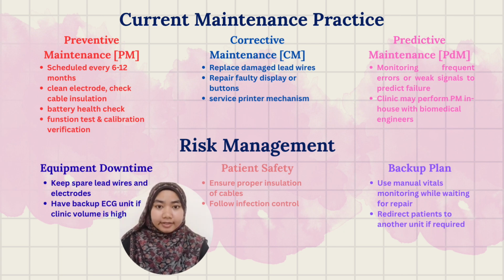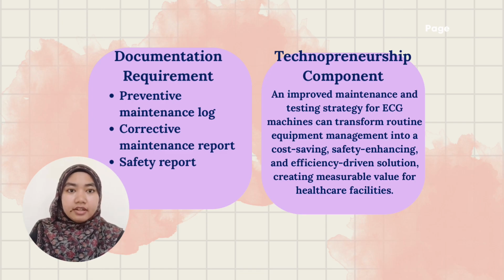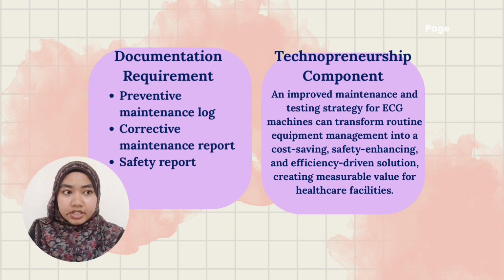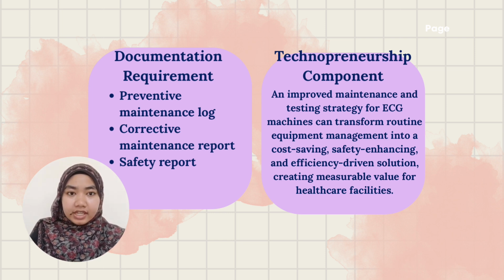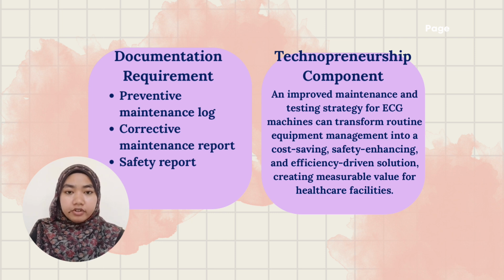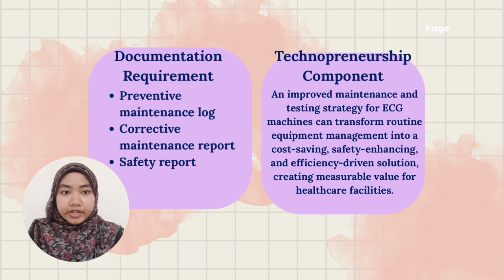For documentation requirements, first is the preventive maintenance log that records routine servicing and inspection of the ECG machine to prevent breakdown and ensure proper functioning. Next is the corrective maintenance report that documents repair and part replacement when the ECG machine fails or malfunctions. The last one is the safety report that records electrical safety tests and checks to confirm the ECG machine is safe for patient use.